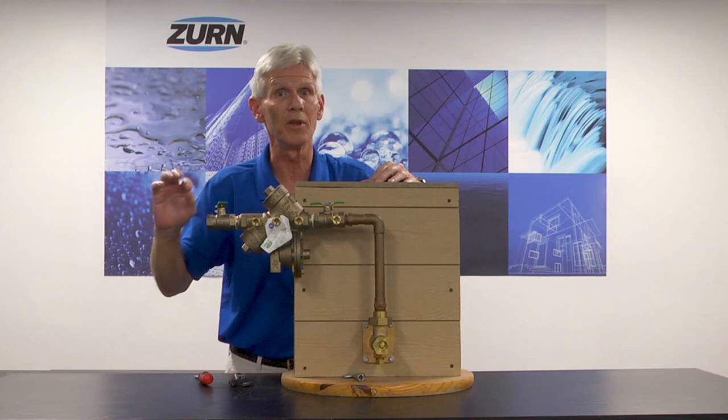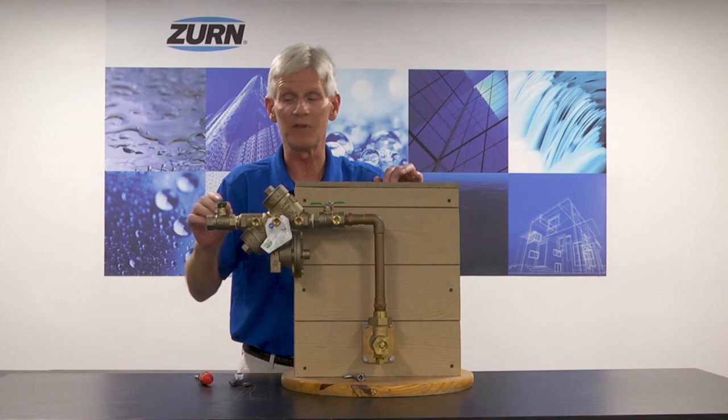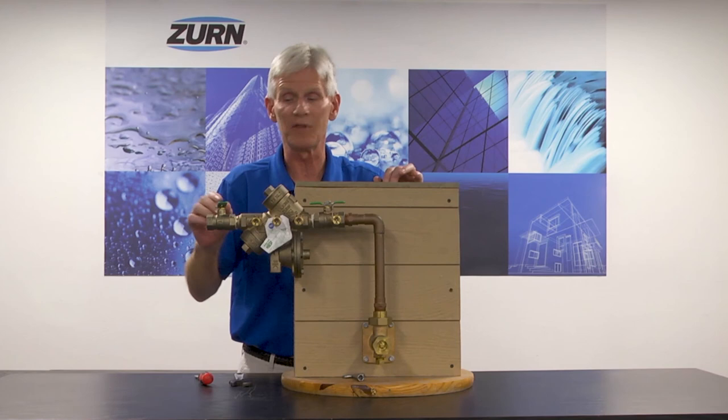Next, we'll go ahead and crack open our downstream ball valve and slowly pressurize the downstream system. It will be evident to you when it's full because as you're filling you will hear the rush of water moving through that ball valve, and eventually that will calm down and be quiet. At that point in time, we know we have the downstream system filled and we can continue to open our ball valve fully.